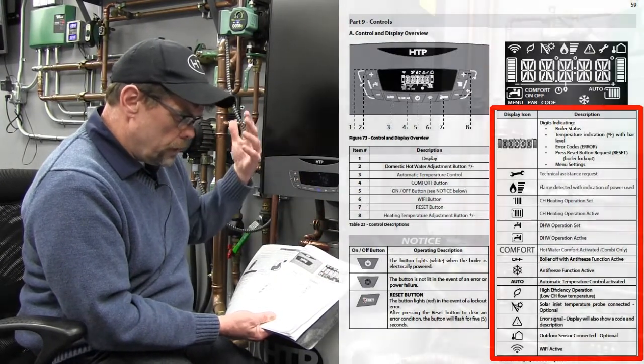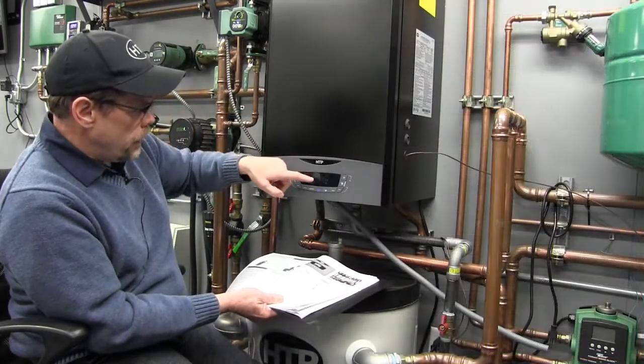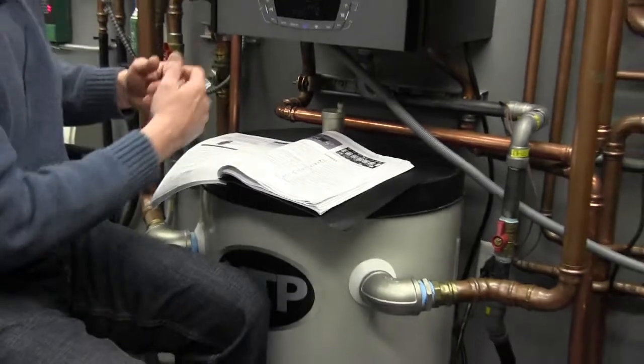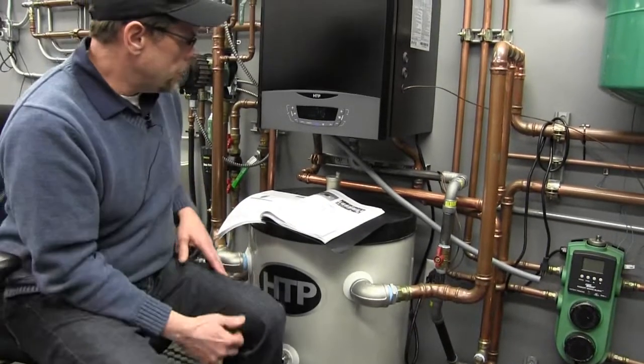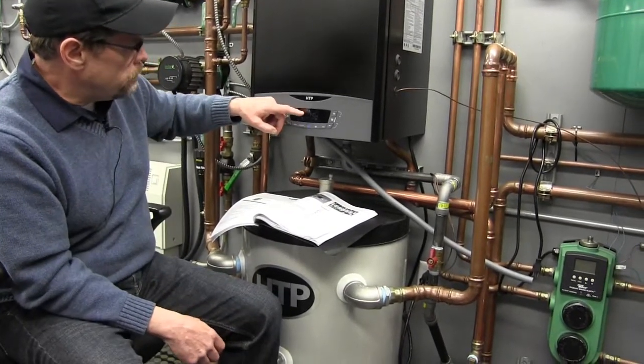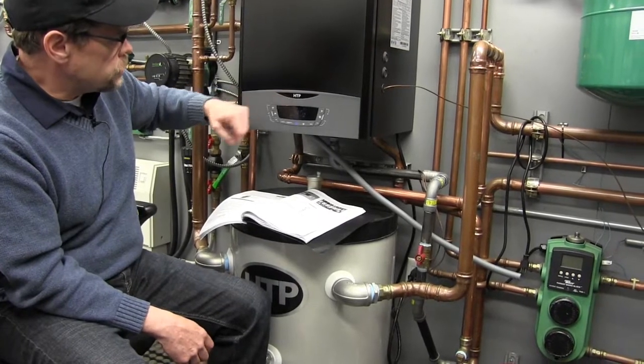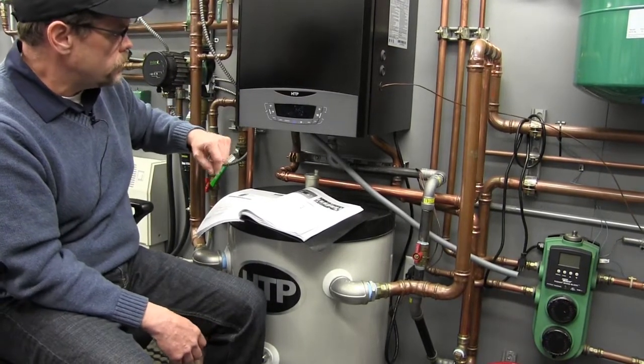The next one will be whether or not we have detected a flame. Quick glance at the display, we can see what the boiler is letting us know. In this case, it's telling me my flame has been proven. It's on low fire. It's 145 degrees.